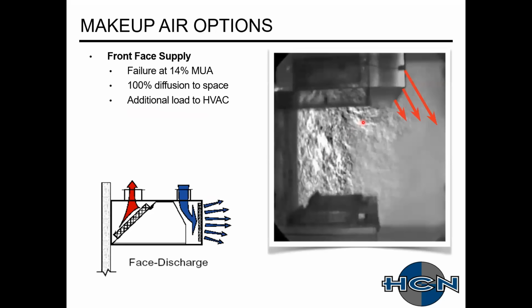Front discharge hoods. Typically, the air on this one didn't really get the memo that it needed to go out into the space, turn 90 degrees, and go right back into it. Basically, you're putting pretty much 100% load onto the HVAC, depending on what kind of makeup air. If you're just doing an untempered unit, that's complete load. In the winter months, let's say you're doing a direct fired heated unit. In the summer months, a lot of humidity gets stuck into those HVAC returns.